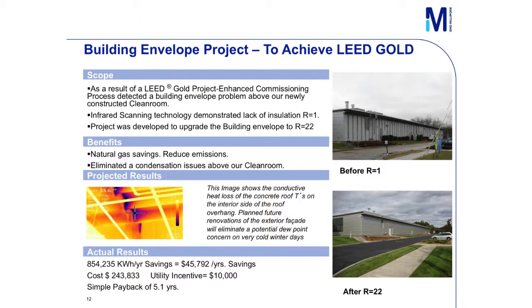Right away we said this is going to be a huge problem because we're probably going to have a moisture issue above our clean room. Moisture in clean rooms leads to mold - not a good thing. So right away this keyed us in, and we said we really need to address the insulation on the building.